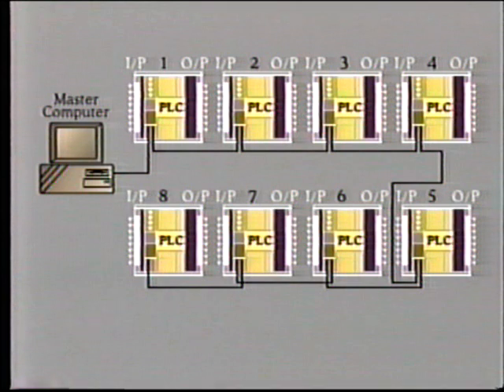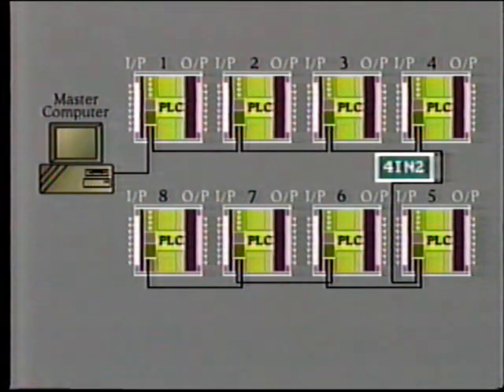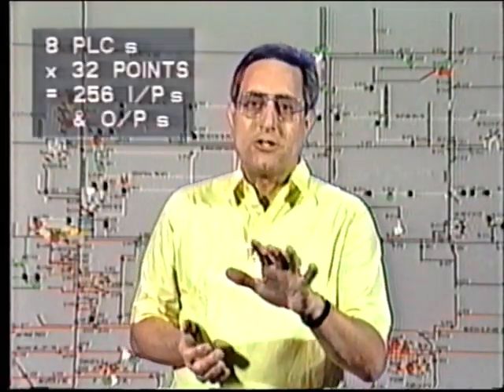In order to clearly identify data from each of these PLCs, it is necessary to assign a number to each individual controller. Typically, then, a specific input address may read, say, 4IN2. This would mean that the addressed data point is on number 4 controller, and it is input point number IN2. This particular system, which loops 8 PLCs, provides a total of 256 input and output points. That is 32 points per controller. However, there are a number of systems available which provide much greater capacity than that.